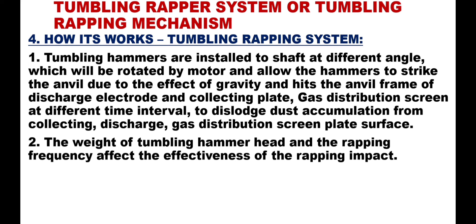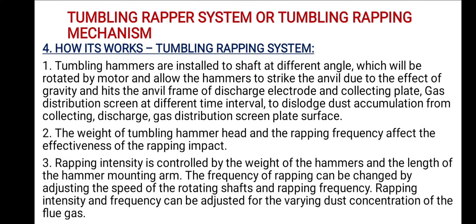Point 4 – How the tumbling rapping system works: Tumbling hammers are installed on a shaft at different angles, which are rotated by a motor and allow the hammers to strike the anvil due to the effect of gravity. The hammers hit the anvil frame of the discharge electrode, collecting plate, and gas distribution screen at different time intervals, to dislodge dust accumulation from the collecting, discharge, and gas distribution screen plate surfaces.